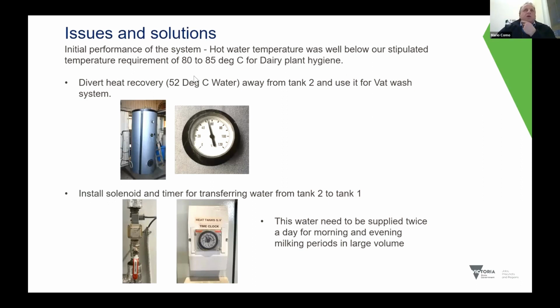Yep. So in terms of the initial performance of the system, the hot water temperature was well below the stipulated temperature requirement of 80 to 85 degrees for the dairy plant to maintain hygiene. So the first thing we did: we had the heat recovery from our chiller, which is about 52 degrees going into tank 2. We took that heat recovery away, and we're using that heat recovery water in our vat wash system. That was because the heat pump was switching off. It was reaching 60 degrees on tank 2 and switching off because of the return loop reaching 60 degrees.